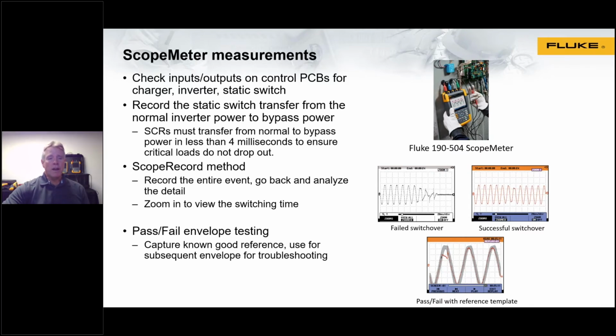It can also be used to quick check that static switch transfer from the normal inverter power to bypass power. The SCRs have to transfer that power pretty quickly, typically in less than 4 milliseconds, to ensure critical loads don't drop out. So a scope meter can make a great tool to be able to show that. We have an example of that where we have both a successful switchover on the right side. We see that there is not a dropout. You can observe that, yep, there was a switch over here, but we didn't lose power at all. And here we have an example of a failed switchover. So that would be one method.